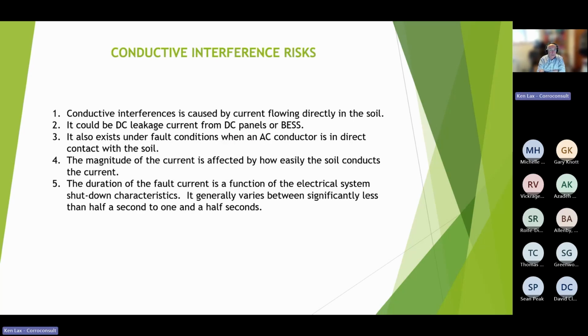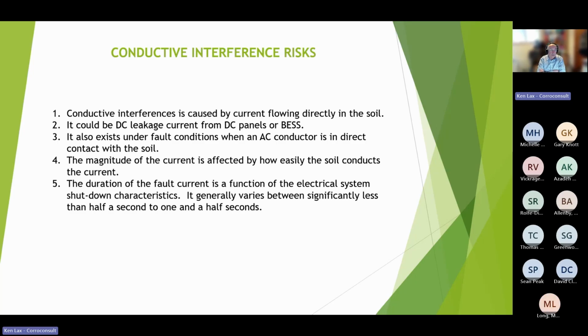Conductive interference is exactly what it sounds like. It's conducted through the medium between the source and the recipient. So in this case, it will be the soil. The electricity travels through the soil onto the pipeline, and it changes the pipeline voltages and performance. And the conductive interference normally only occurs during fault conditions, which is when you might have one of the cables break on your overhead line and it falls to the ground, and that current travels through the ground, hits the pipe and generates upstream and downstream until it finds the compressor station or any above ground area where there's isolation.